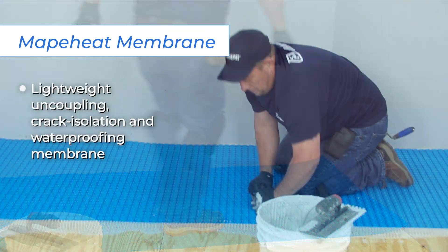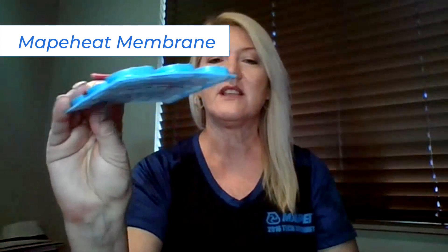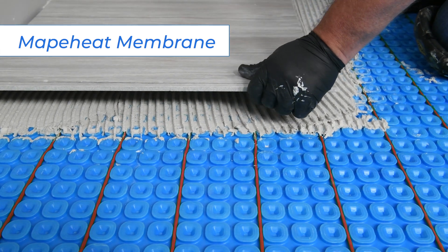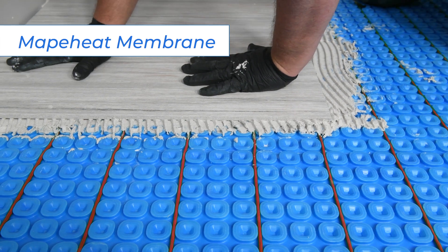The next item in the family is Mapeheat Membrane. This is a lightweight, uncoupling, crack isolation and waterproofing membrane that features rounded square reliefs into which the Mapeheat radiant heating cables securely snap. The membrane's thin profile of less than a quarter inch or six millimeters works well with remodeling projects in which a new floor is installed directly over a pre-existing one. The rounded squares really do make it easy to snap the cable in place — that cable's not going anywhere when you trowel over it with mortar. That snap lets you know that the cable is locked in there.